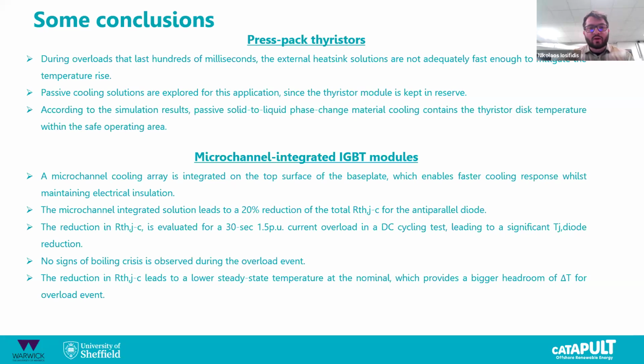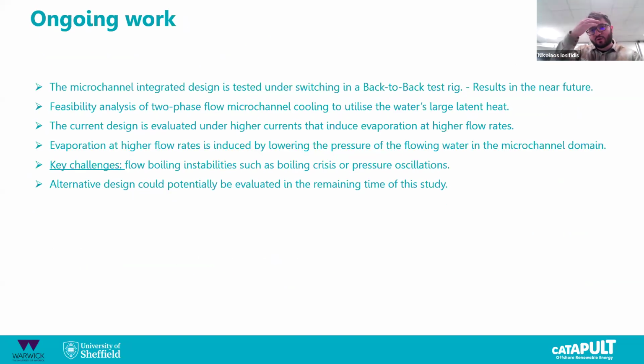And for microchannel cooling, we have reduced the junction to case thermal resistance by 20%, which can be used to increase the nominal current operation by 20% in steady state. Or it gives you a bigger headroom if you want to inject more current, and you can reduce the maximum temperature below the maximum limit. And the next slide is the ongoing work.